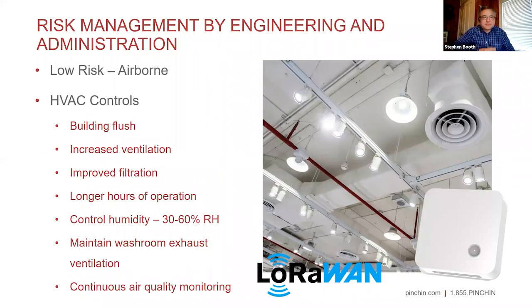transferring the infection to someone else. But on cost-effective HVAC, flushing the building prior to occupancy, running the air handling systems a little longer, increasing ventilation, improving filtration, and not necessarily changing filters or the type of filter, but making sure that the filters you have in the building are operating as well as they can, so there aren't gaps and those kind of things that are allowing air to bypass the filters. Those kind of things can be done ahead of time and can be constantly maintained.